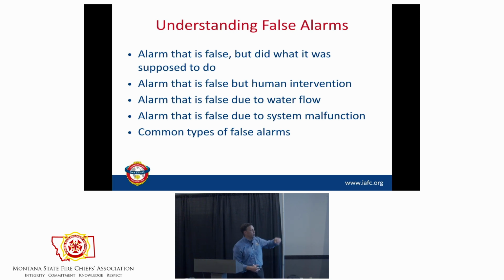Alarm that is false, but there was human intervention. So that's me pulling a pull station, a kid bumping into it, right? So how do we solve that situation, right? If we have a pull station that's always getting bumped and pulled, or we have an Alzheimer's wing where they pull the pull station to unlock the doors, are there things we can do? And there really are, right? We can put protective covers that sound an alarm. They're listed, they're part of the appliance, right? We can go that way, or we can add other layers.